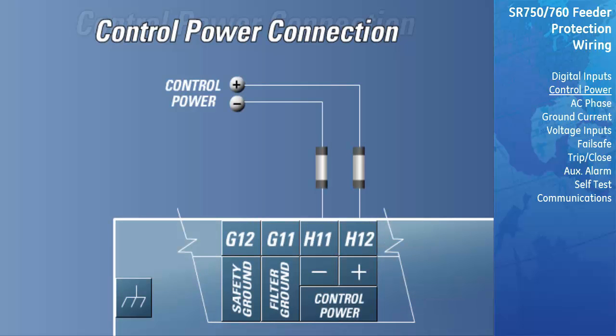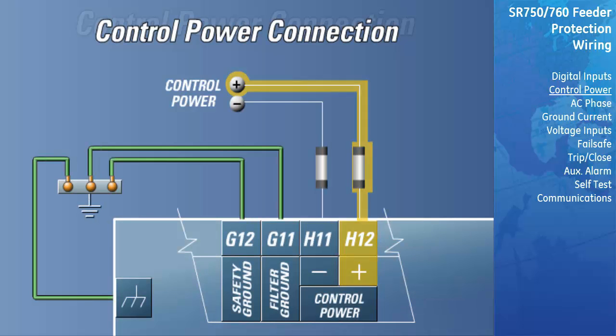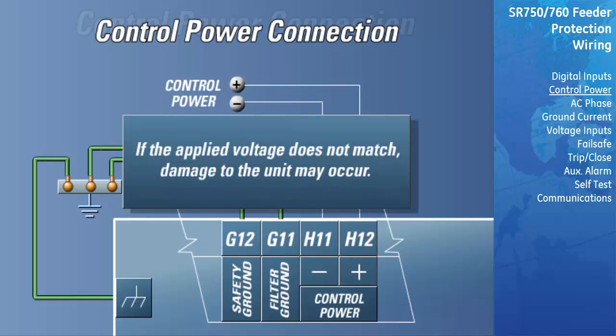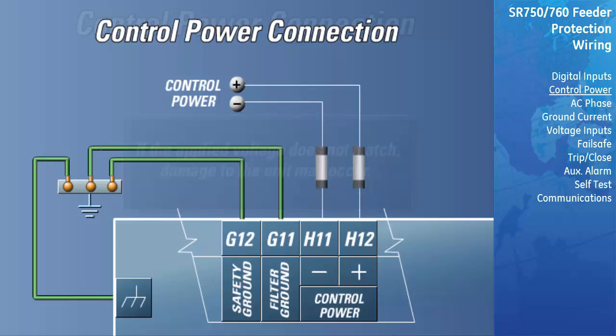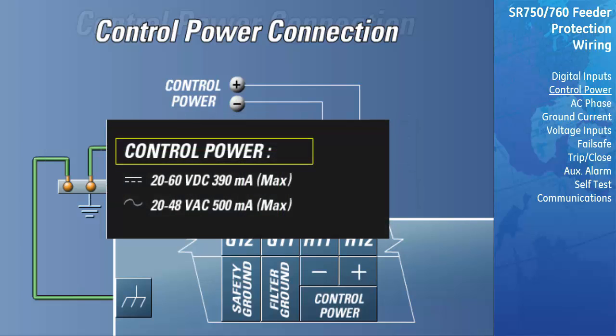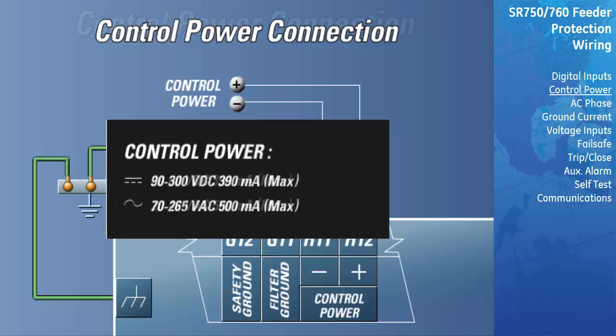The control power supplied to the relay must match the installed switching power supply. If the applied voltage does not match, damage to the unit may occur. The order code on the terminal label on the side of the drawout unit specifies the nominal control voltage as one of the following. For low voltage connection, the label will read Low 20 to 60 VDC, 20 to 48 VAC. For high voltage connection, the label will read High 90 to 300 VDC, 70 to 265 VAC.